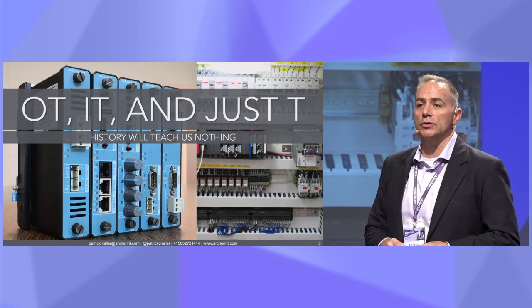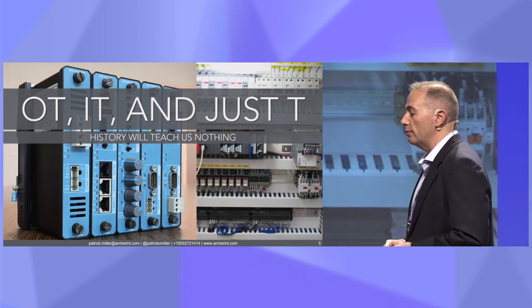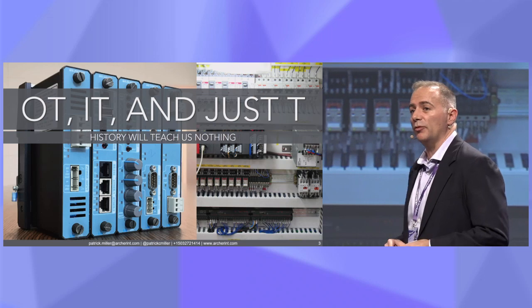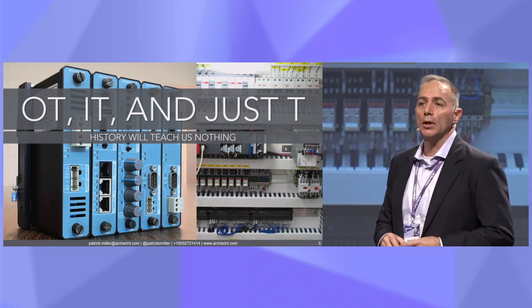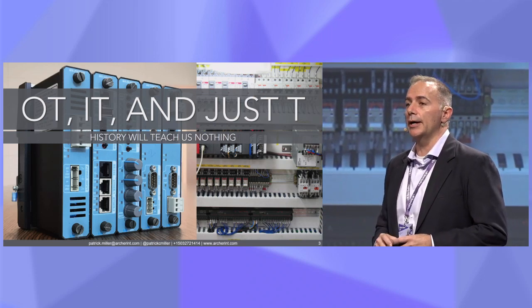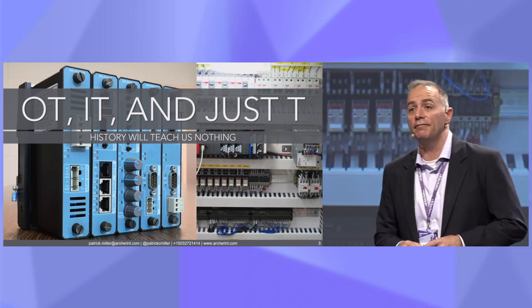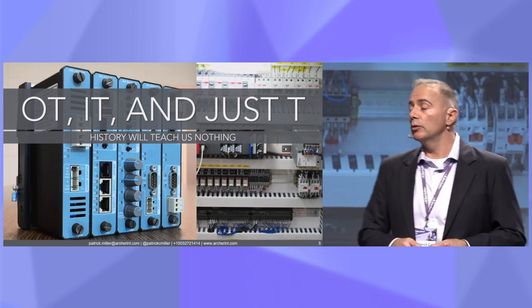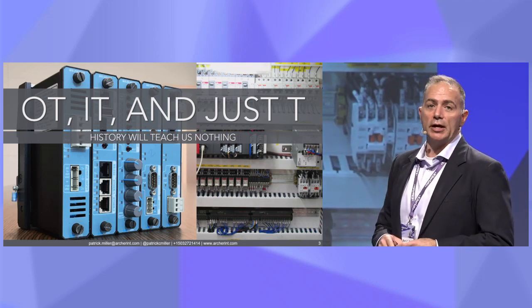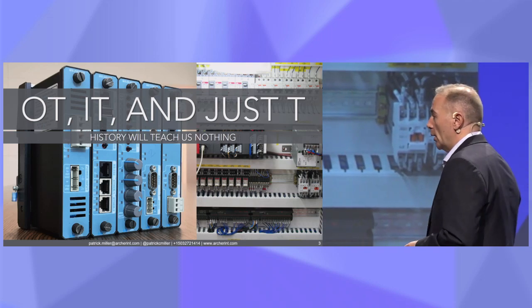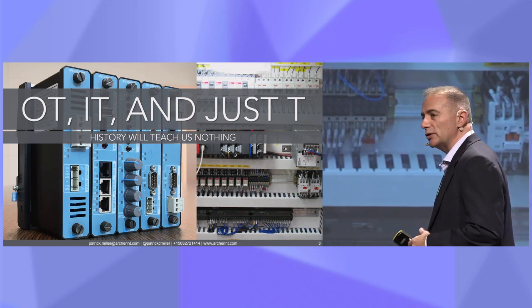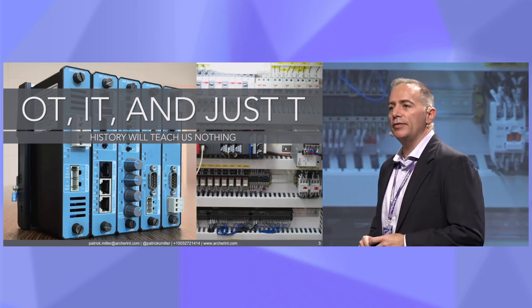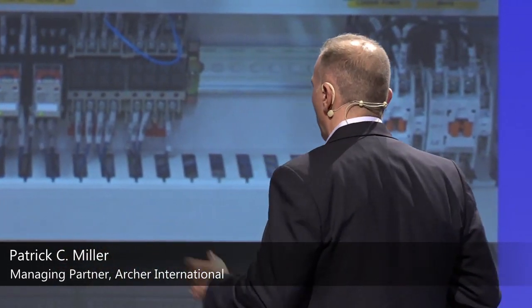I've even been in installations that are still operating today that run, for example, things like Conitel protocols on 300 baud, twisted pair copper. This stuff's been running for a very long time. It's designed to run for 20, 30, 40, 50 years or longer. It was built for reliability. It was not built for security. It was never designed to be connected to anything. So these little tiny purpose-built dumb computers, that's what they do. They literally sense something and report back what they're sensing, or maybe you can send a command to it and it will operate a lever or move something, open a valve, open a breaker.